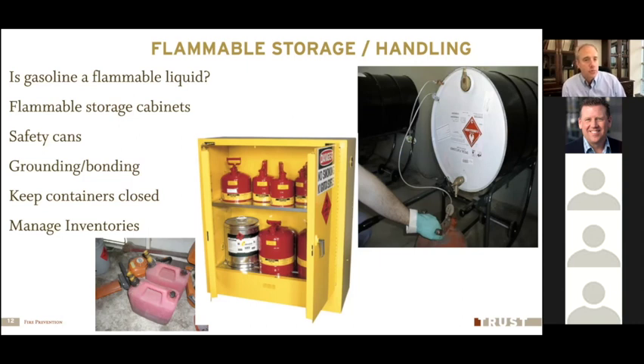We want to make sure that when we're using fuel, transferring fuel, filling tanks, that we're grounding and bonding that equipment that we're using to transfer that fuel, because all it takes is a static charge, one static spark, around the vapor of that fuel while we're fueling a piece of equipment or putting fuel into a portable gas can to start a fire. And so make sure that your portable gas cans are grounded on the ground, not in the back of a vehicle, before you fill them, and make sure that you have some procedure in place for grounding or bonding your pumping or other fuel transfer equipment when you are putting fuel in your equipment.